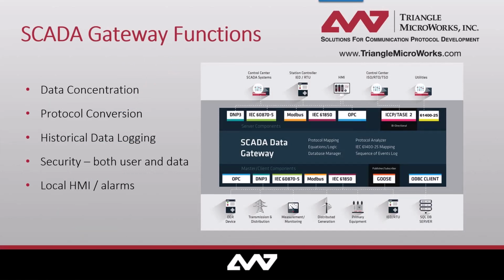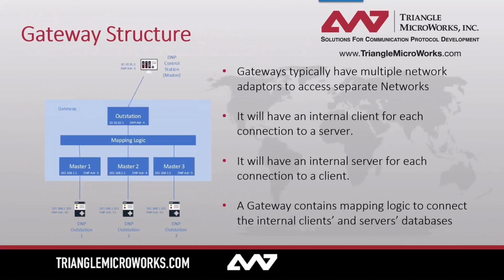So now let's talk about some of the functions you'd expect gateways to have. Not all gateways will have all of these functions, and you would expect a large percentage of them, though, to have at least one or multiple of these functions. The first one we're looking at today is the data concentration. That's actually what we were just looking at here. Data concentration is when you take data from across multiple different devices, and then you put it all through this mapping logic into a singular database, and then you can present that database up to your DNP3 or your control station, whatnot. So you're concentrating the data across your entire substation into a singular database, which you're presenting to your HMI or your SCADA Master.